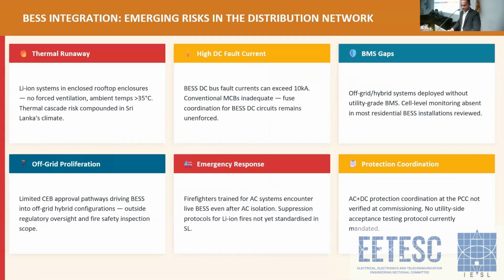Then I will talk a little bit about the BESS. BESS, the battery energy storage system concept, is not properly in place. That requirement is there. I would explain in my next slide how important battery energy storage is for us, especially for the Ratmalana area. Our presenters, and our engineer Amila also, explained the battery requirements and the safety requirements of battery storage, because it's going to be really tough to properly look after batteries. There is a huge fire risk, because they are always exposed to high heat.